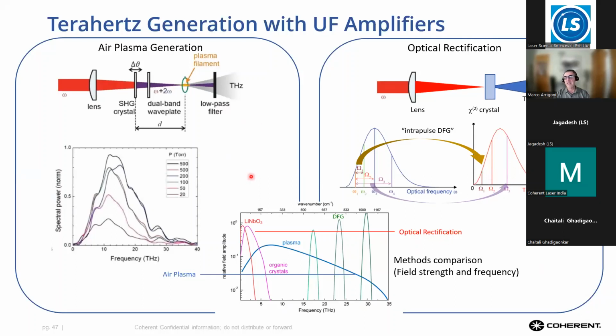There are basically two competing ways to generate powerful terahertz pulses. One is to send an amplifier into a second harmonic crystal and combine in air the two beams - the second harmonic beam and the fundamental beam - creating a plasma filament that generates a very broad spectrum of terahertz, which can extend to 30 or 40 terahertz.